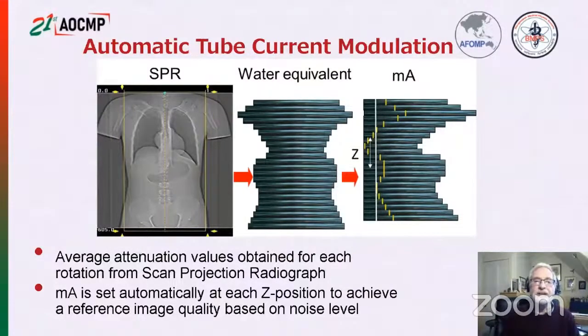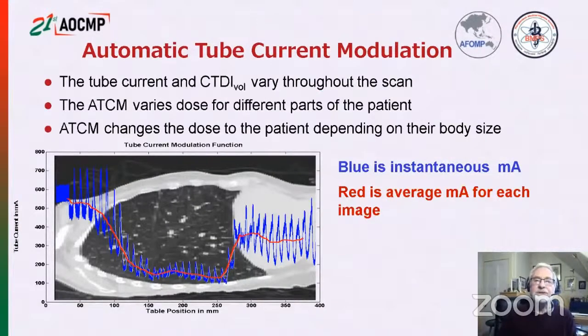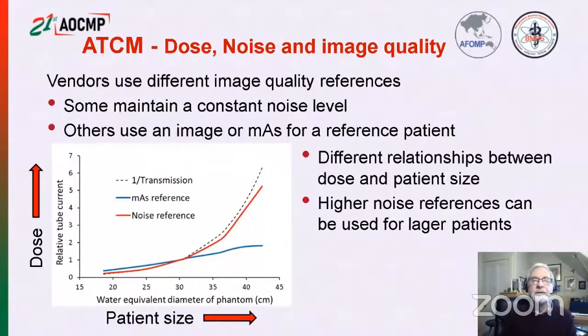And there's automatic tube current modulation, where the average attenuation value is obtained for each rotation from the scan projection radiograph to vary the mA automatically along the body. So this shows how the tube current varies, and so in the area of the lung, a lower tube current is used because it's a lower attenuation. So the ATCM changes the dose to the patient depending on their body size as well. And in fact, different vendors use different image quality references. So some maintain a constant noise level, whereas others use an image or mAs for a reference patient. And I've plotted here the dose against patient size, and systems that use a noise reference, if that isn't changed for larger patients, can give significantly higher doses.